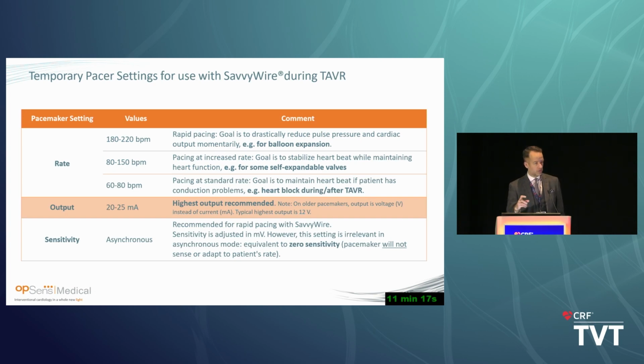Sometimes for your self-expandable valves, you're going to go a little bit higher than that. Again, usually there's no issues with capture there as well, and then for rapid pacing for your balloon expandable valves, there's no problems there as well. The highest output, like we just mentioned, is recommended, but just make sure you test it and find out where your capture level is lost. And for your sensitivity, it's recommended to be asynchronous while you're using this.